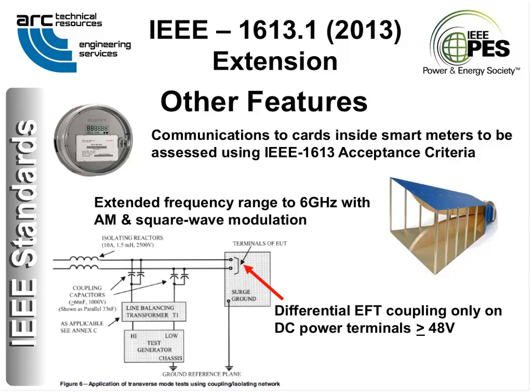Also, differential fast transient coupling is now run on DC power terminals at or above 48 volts only. This is to simulate switched armature coils that back EMF arc across the floating station's battery terminals. This was a known source of disturbances originally addressed in C37.90.1 back in 2002. Very few people make this line balancing transformer T1. We actually wanted to get rid of this test, but we can't. It's an actual legitimate test, so if you need a line balancing transformer, you'll have to wind one. Good news, the instructions are included in the document. Bad news, it's not as easy as it looks.